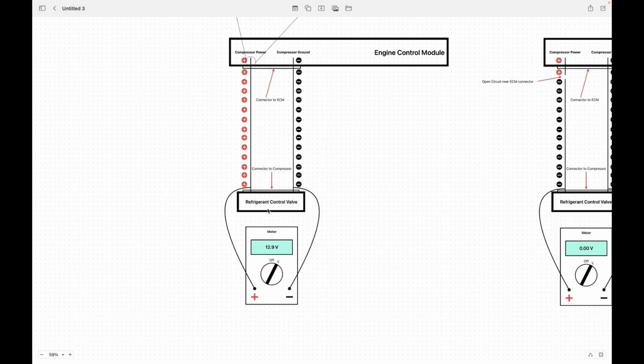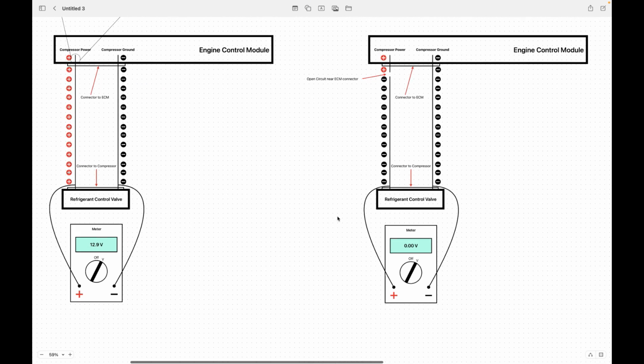Because if, let's say, I had a connection issue anywhere from the module itself to the connectors to the wires to the valve on either leg, I would not see nearly as much available voltage to the valve with the AC system turned on. And so then that would prompt me to look for one of these following scenarios.